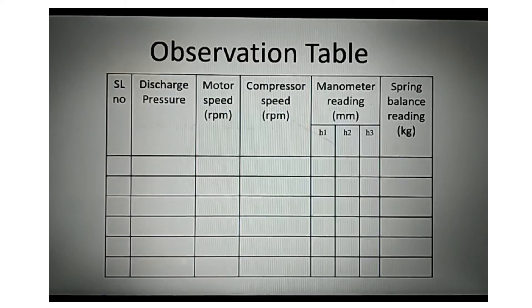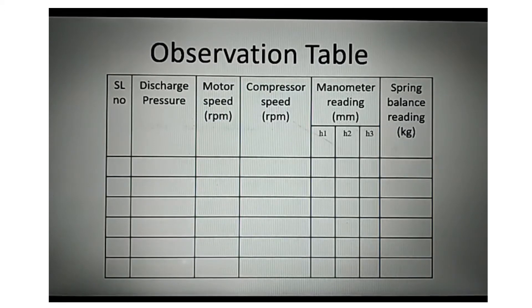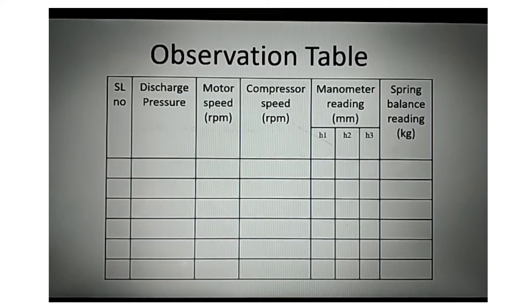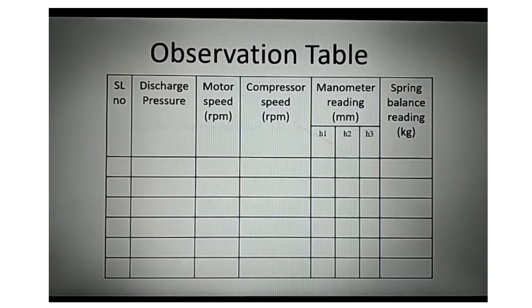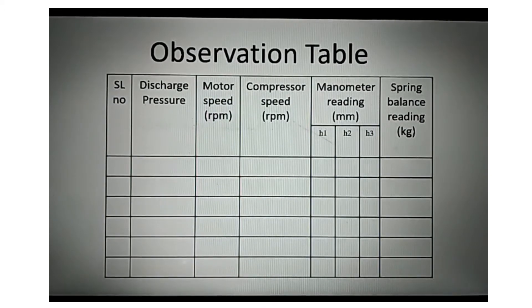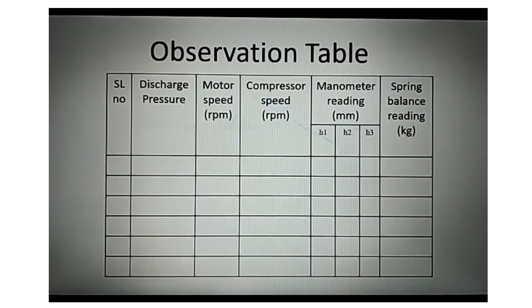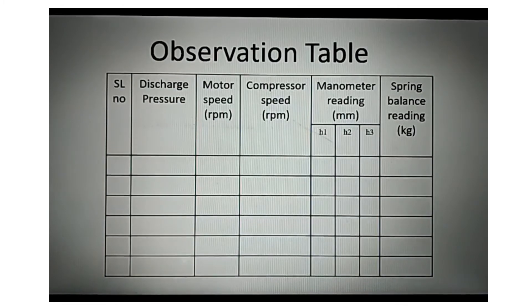Here we can see the observation table. We have to control the delivery valve for getting the observations. You have to note the discharge pressure, and then correspondingly you will get the motor speed, compressor speed, manometer head reading, and also the spring balance reading. The manometer reading is used to find out how much volume of air is compressed in the compressor — you get it in terms of water and have to convert that into air.